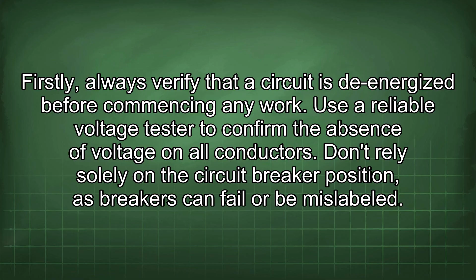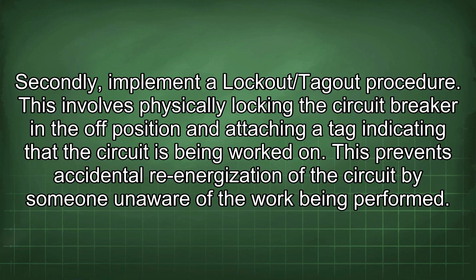Secondly, implement a lockout/tagout procedure. This involves physically locking the circuit breaker in the off position and attaching a tag indicating that the circuit is being worked on. This prevents accidental re-energization of the circuit by someone unaware of the work being performed.